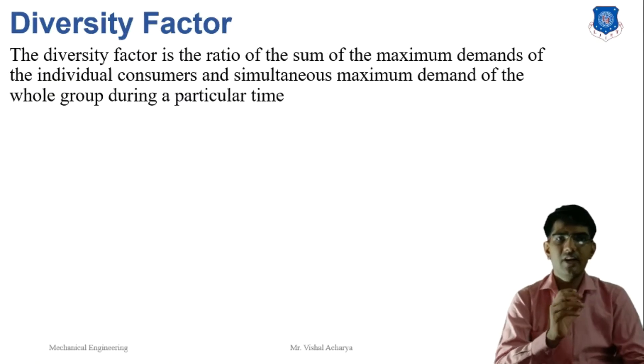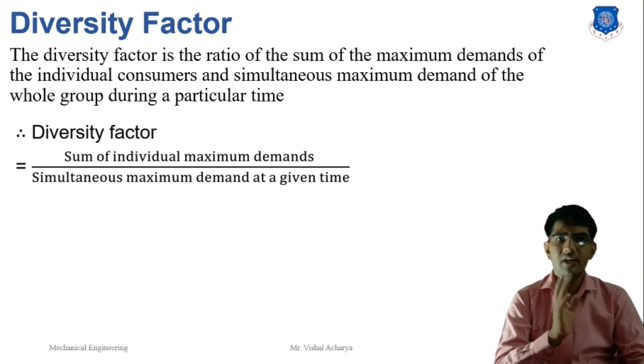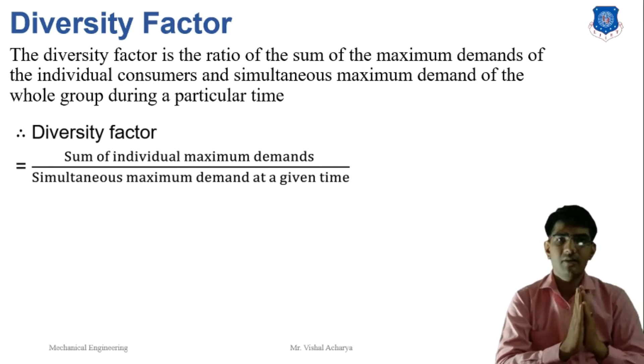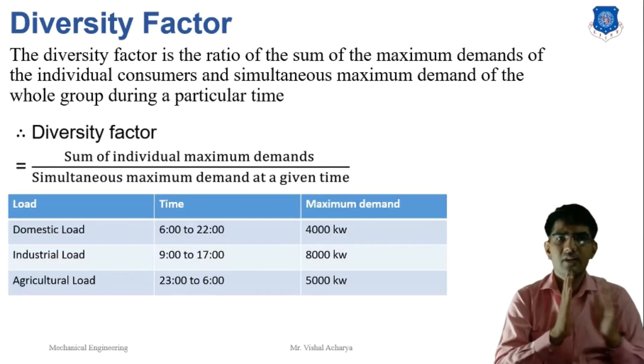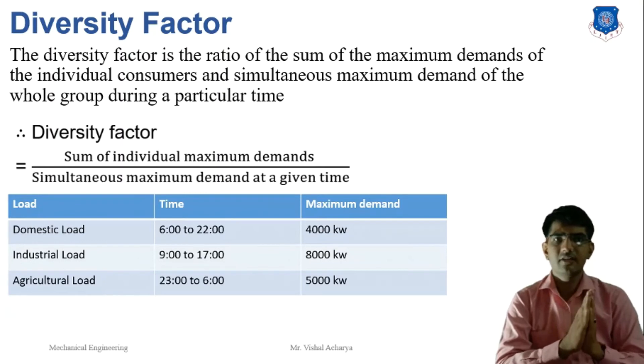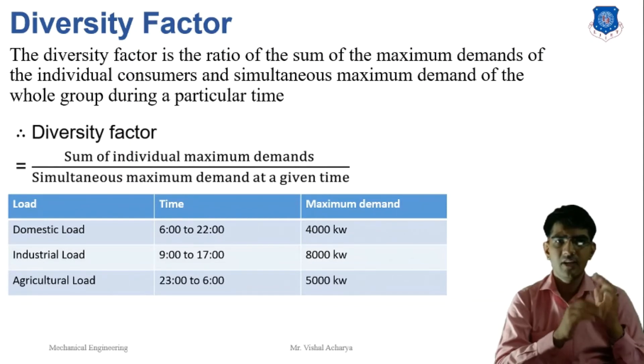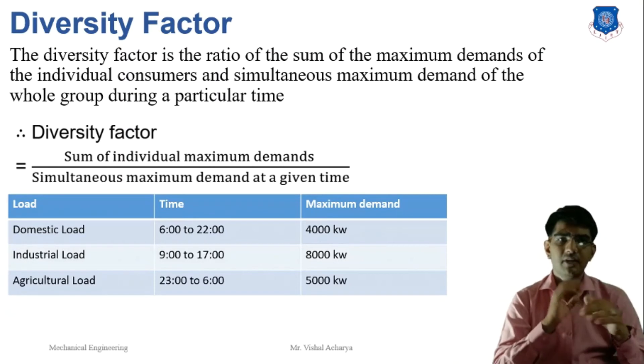The next term is the diversity factor. Diversity factor is the ratio of the sum of the individual maximum demands of consumers to the simultaneous maximum demand of the whole group during a particular time period. Diversity factor = sum of individual maximum demands / simultaneous maximum demand at a given time. The diversity factor is always greater than 1.